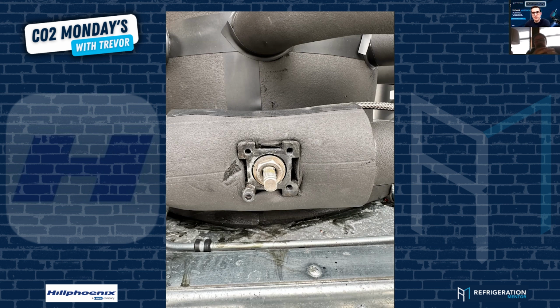Well, Mueller actually had where the valves are inserted 180 degrees. So the vent was actually on the high pressure side. And the symptoms were, you were trying to blow down the separator so that you could change the separator. You would hit about 400 PSI and then something would let loose and you could never stop it from leaking by. We have a bulletin that's out.